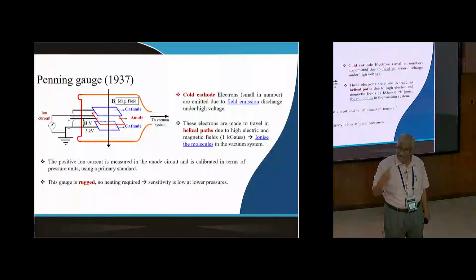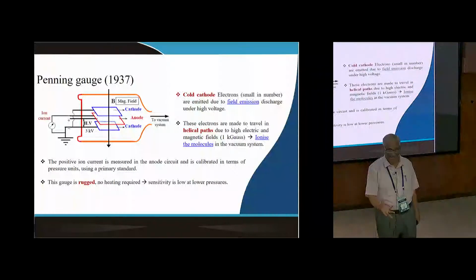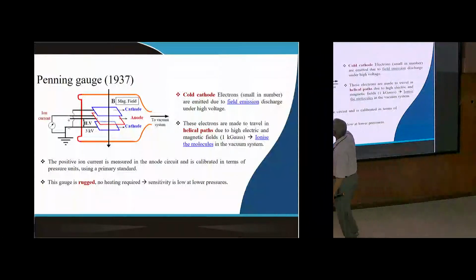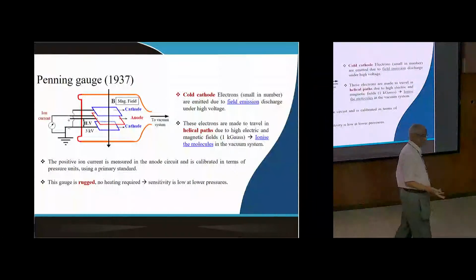In the process, their path length has increased, so their chance of coming across the atoms whose density we want to measure, related to pressure, is more now. Collision cross section is more. Then immediately you start getting ionization. These ions are collected by the anode. That anode current, if you measure, is a measure of pressure by suitable calibration. This is how ionization gauges measure down to 10 power minus 8 torr. Nothing is perfect. If you say 10 power minus 4 torr, I can tell you are wrong, you cannot say anything. It could be minus 3, it could be minus 1.